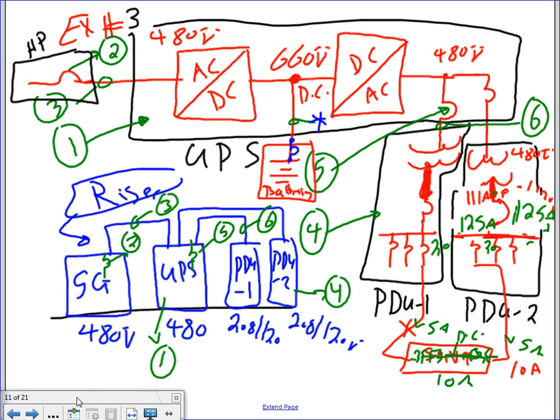So the job of the UPS system, guys, is that if you lose power, your system will not shut down. It will continue to operate for 15 minutes typically. That's enough to start your generators, because generators need at least 10 seconds to start. They can't just come on instantly. You can't drop the load instantly. You lose millions of dollars if you drop the load instantly. So that's what a data center is for, very, very essential systems. Typically finance and security and what's not, all these big companies, the Department of Commerce, the Department of Defense and all this stuff, they have a UPS system.